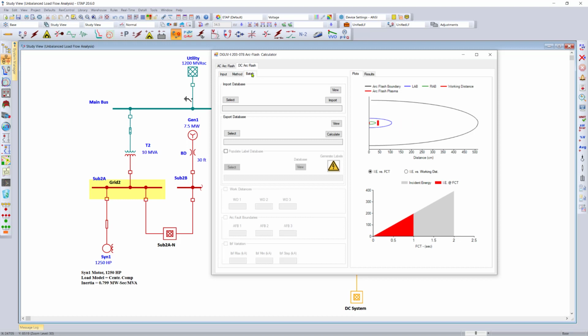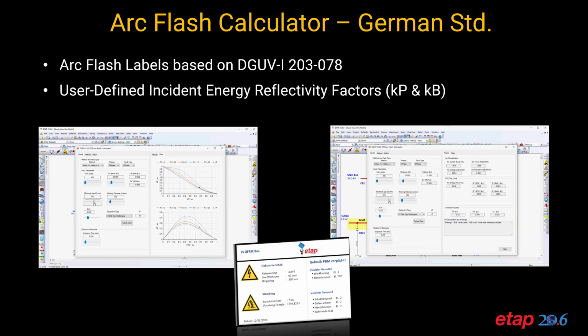Just like with other arc flash analysis tools, the German DC arc flash analysis tool allows you to evaluate thousands of locations by means of importing the batch results from MS Excel and CSV files. DGUV standards do not place an emphasis on labeling as much as NEC and NFPA 70E do, but the tool allows the user to also generate and print labels in Dutch and German languages, which include shock risk approach boundaries based on IEC standards. This new tool pairs up with the existing and enhanced AC German arc flash calculation tool to provide a means to calculate the arc energy based on German DGUV standards.